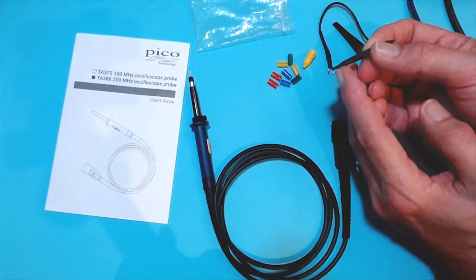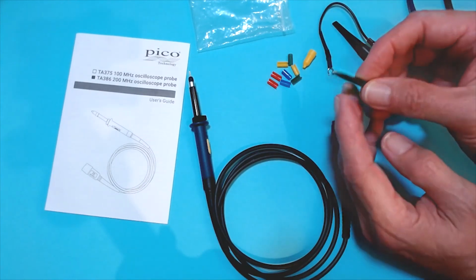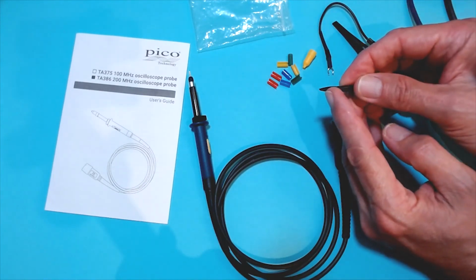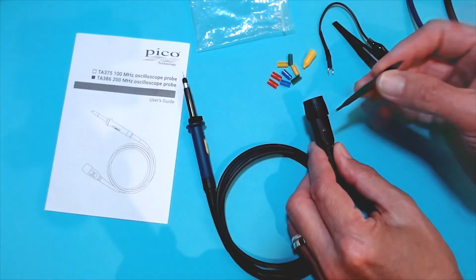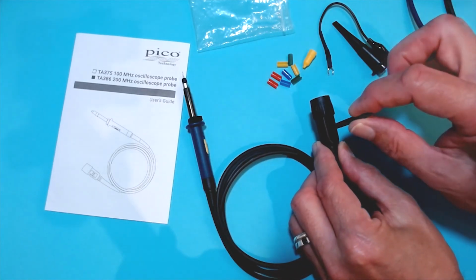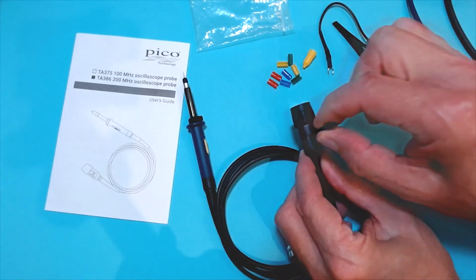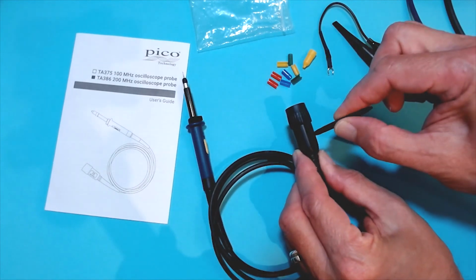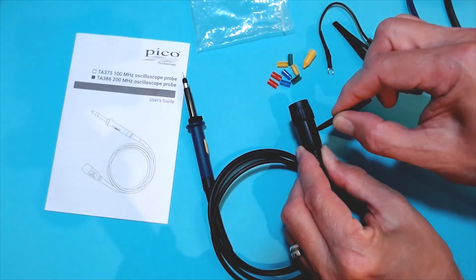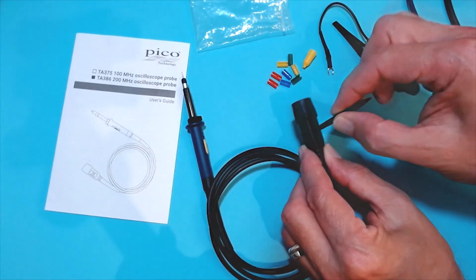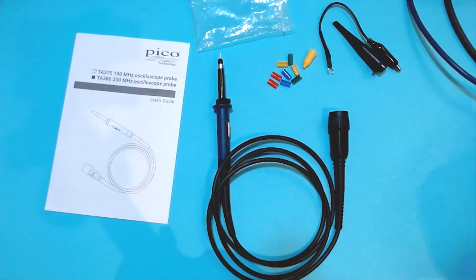This tool is your compensation adjustment tool, with two ends: a cross point end and a flat screwdriver end. Using the cross point end, when you put it inside the chamber you can adjust the capacitance, which we'll look at in detail shortly. That's the compensation adjustment tool.